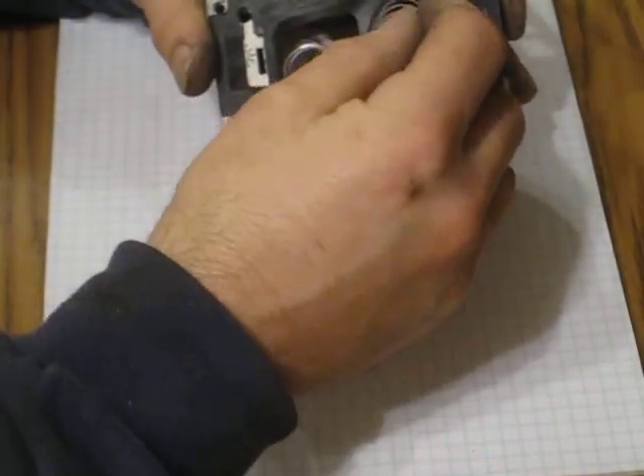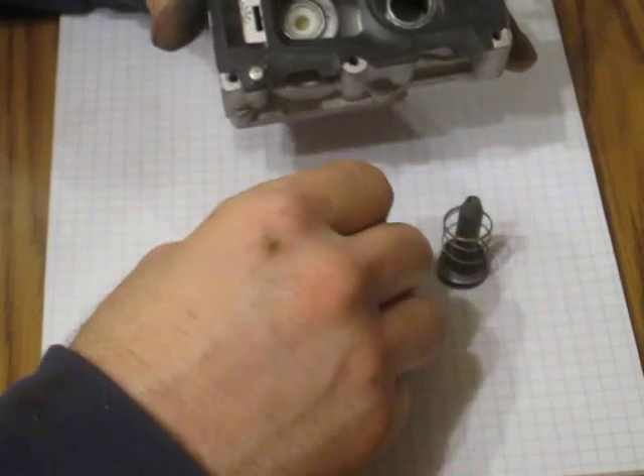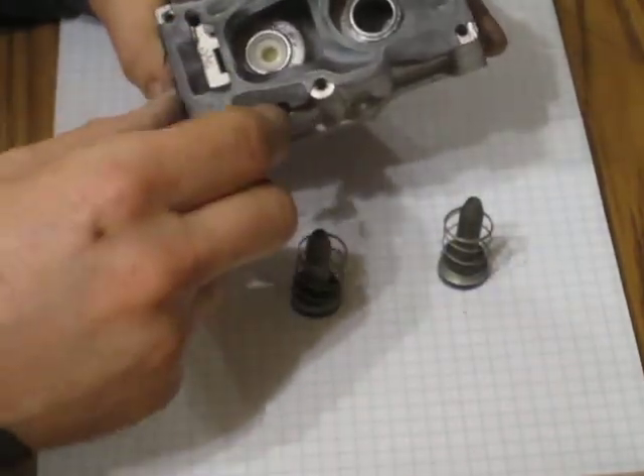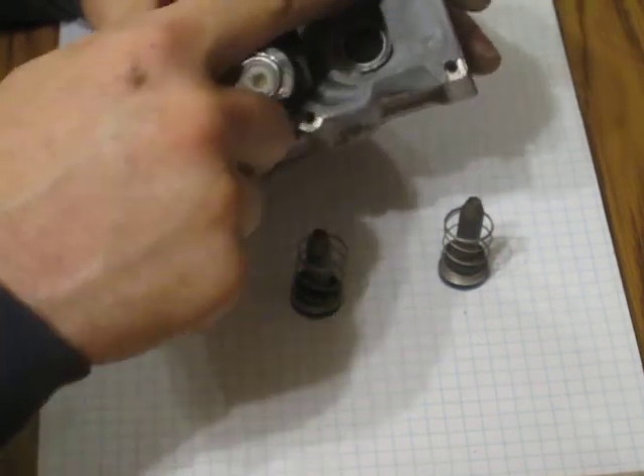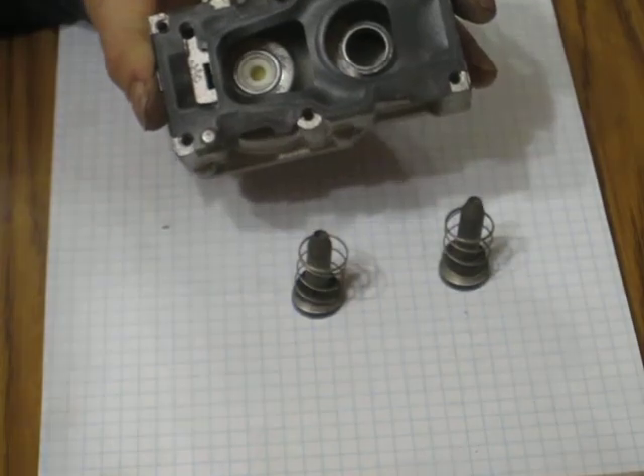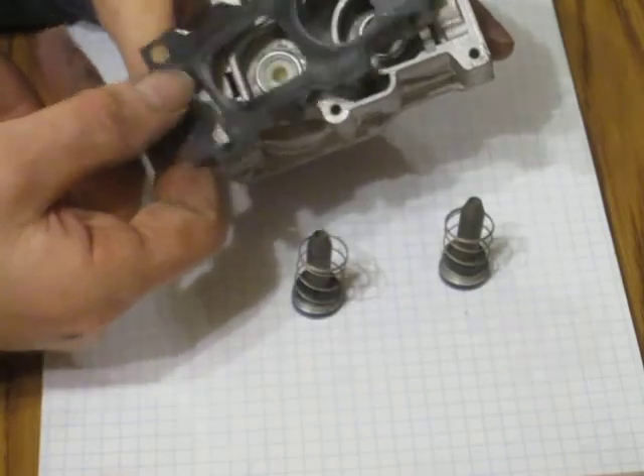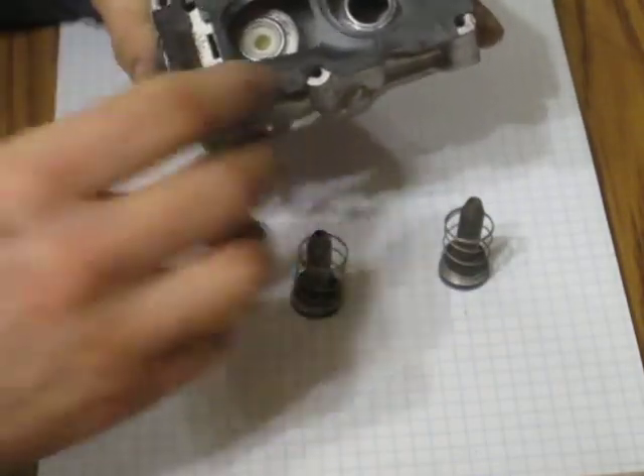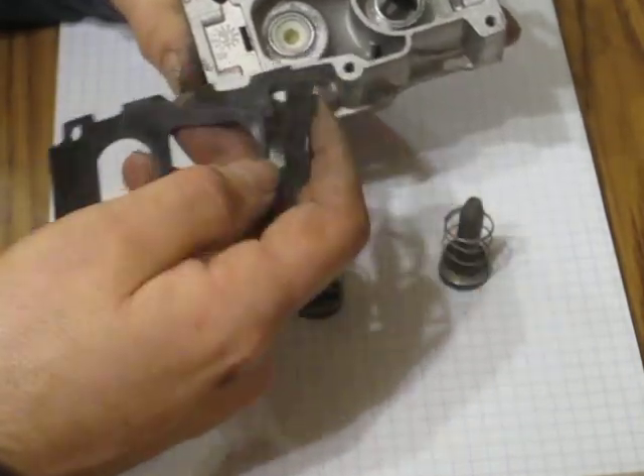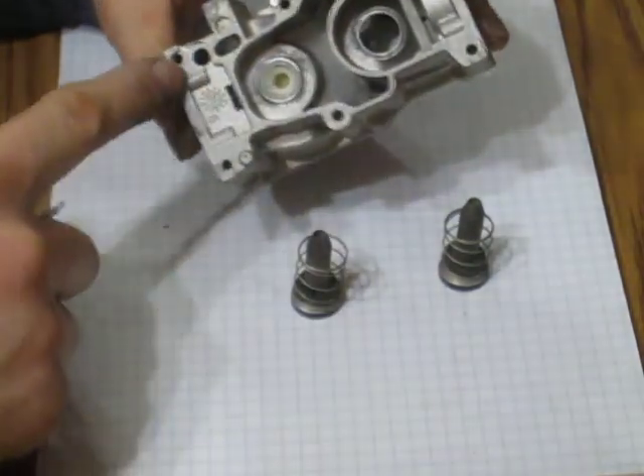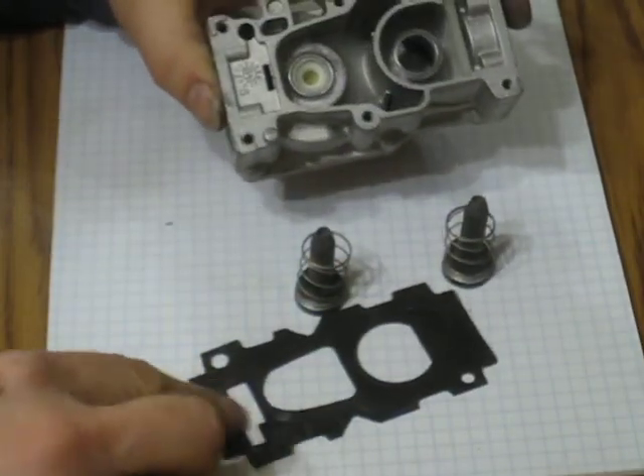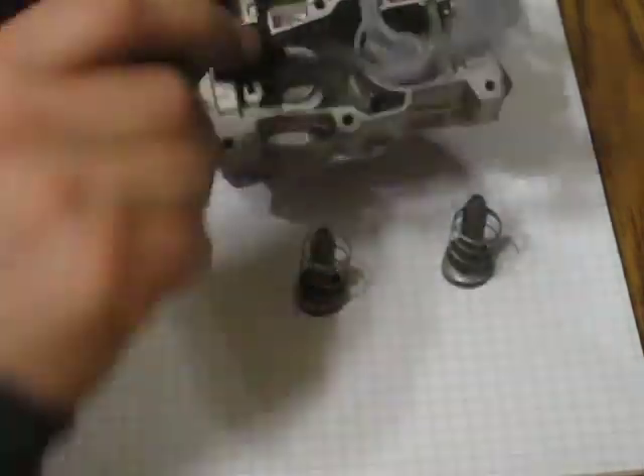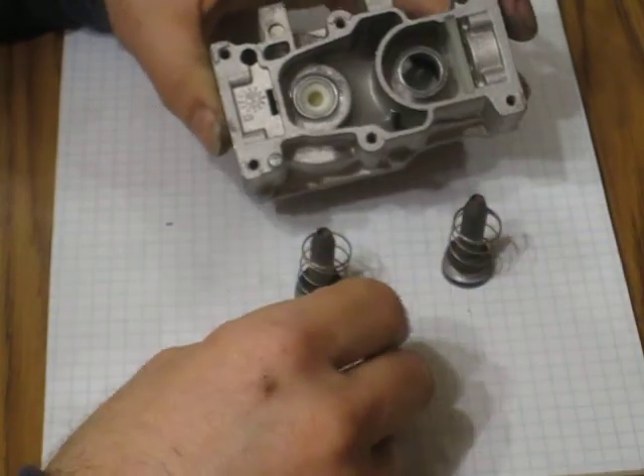When you open this up, you can see the back plate and two solenoid valves and this plastic rubber gasket. It has a correct orientation. There are two pins that allow it to sit properly, so you cannot get it in backwards. Simply will not go properly. You'll probably notice on mine there are a couple indentations here and here, where they run into these little bumps from the screws on the end. Set that aside, make sure it looks good. It should be clean and not torn. I was very careful when removing it to make sure it didn't tear.